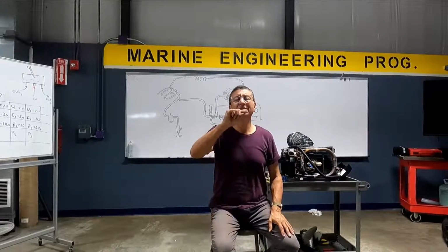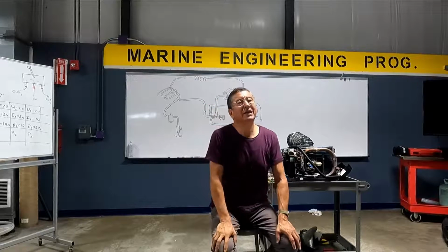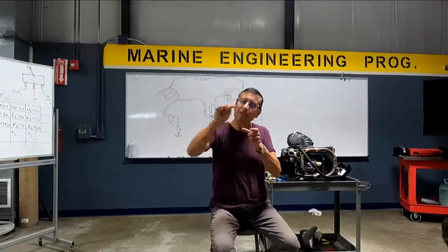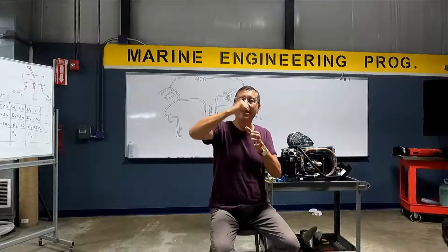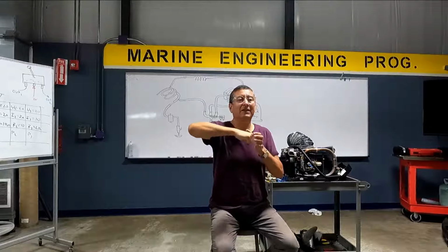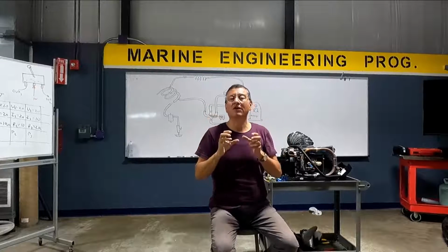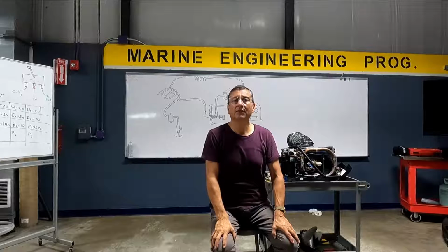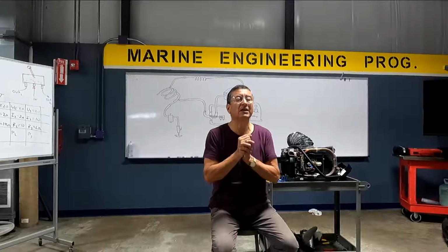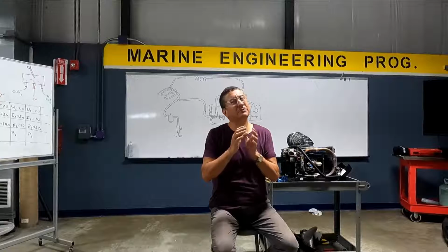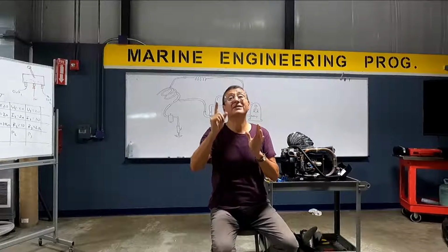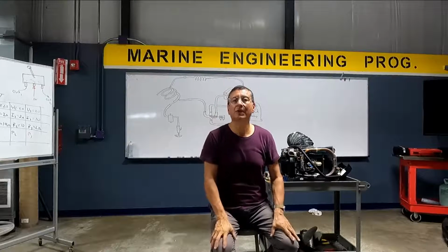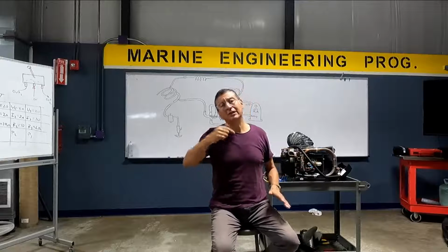I forgot to mention, in marine applications the preferred expansion valve is the capillary pipe. In industrial and residential applications, instead of capillary, they use a thermal valve. The valve opens and closes depending on other factors like pressure and temperature. I am going to explain later. It's the thermal expansion valve, a nice design. In marine applications, they prefer capillary pipes, except in chiller systems. Next week, I am going to explain chiller systems and the thermal expansion valve. But in the rest of the air conditioning it is the capillary pipes.